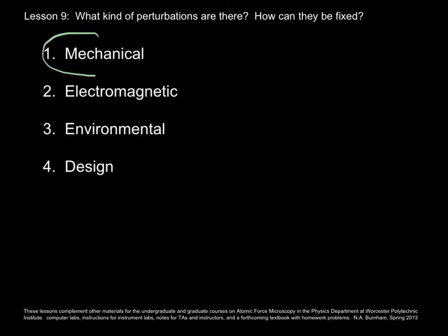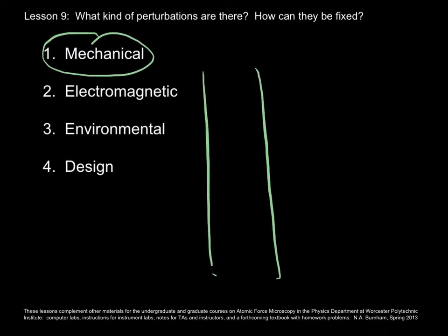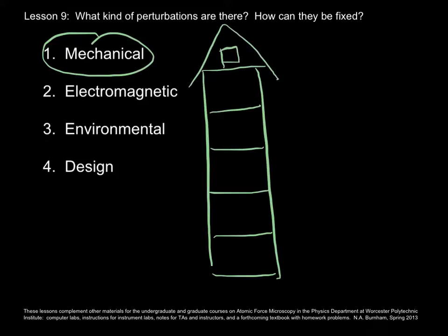Mechanical. Here is a tall building with floors. You do not want to put your AFM on the top floor. Whereas we don't notice the building swaying, the AFM does. So the closer you are to the basement, the better.